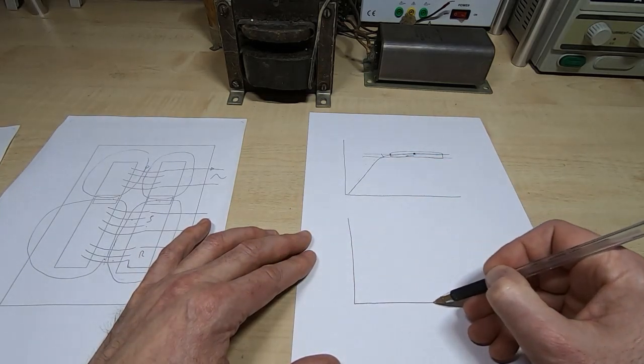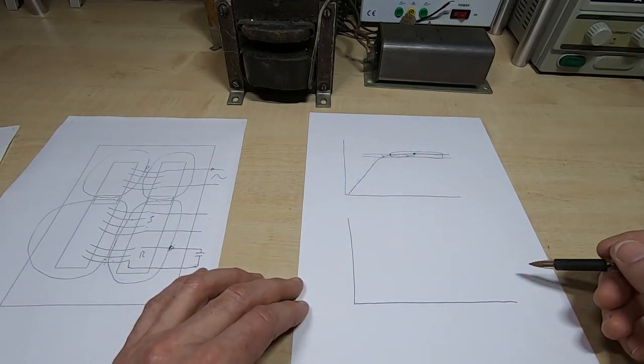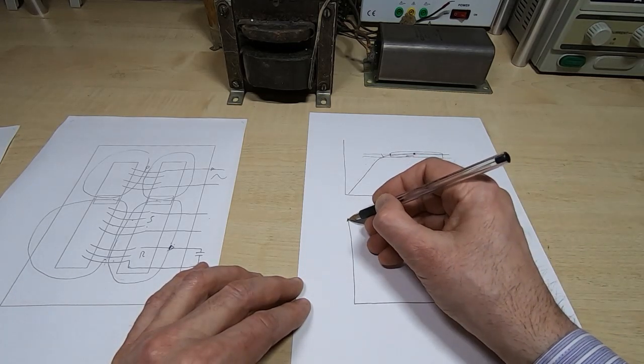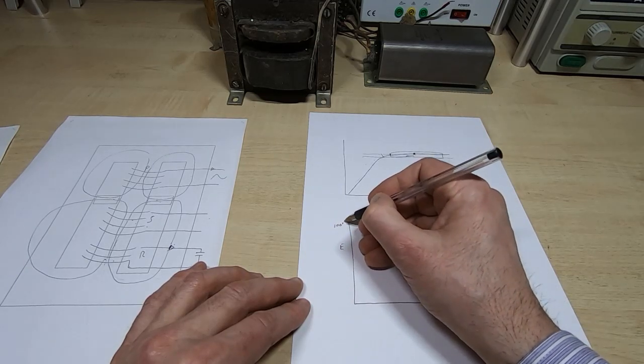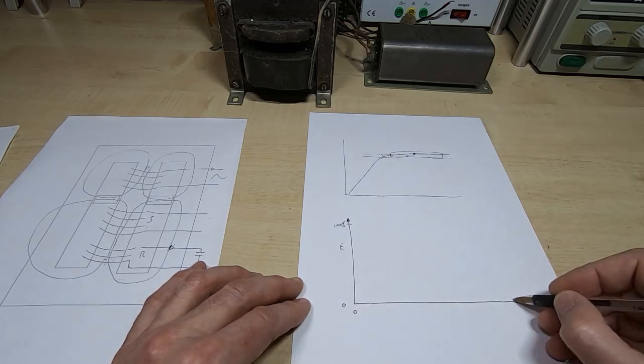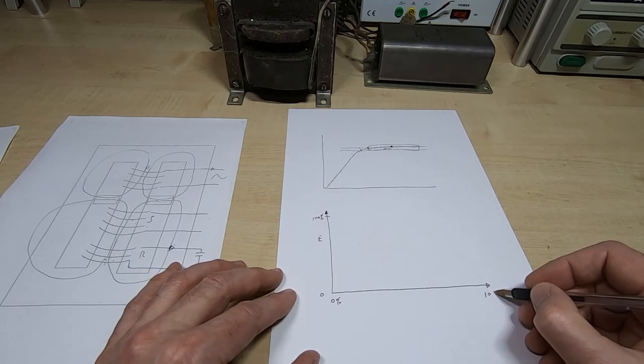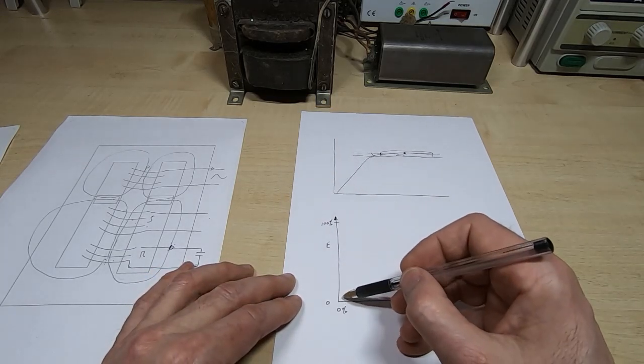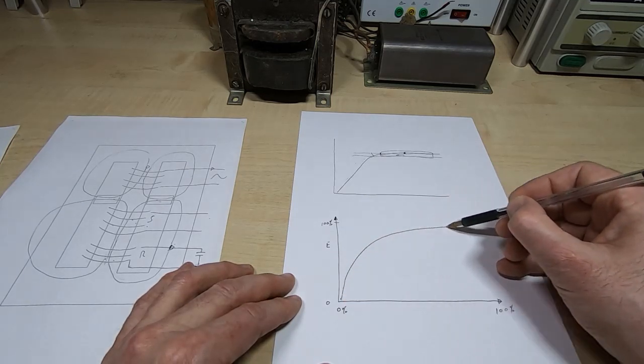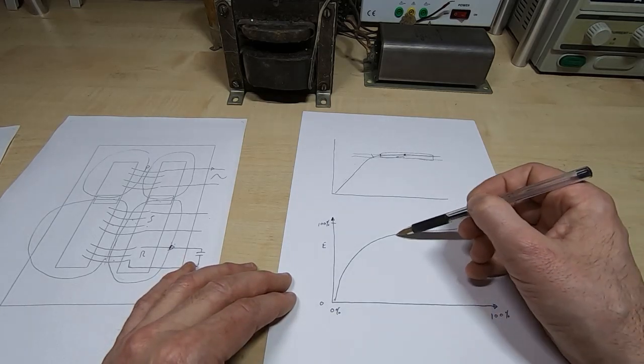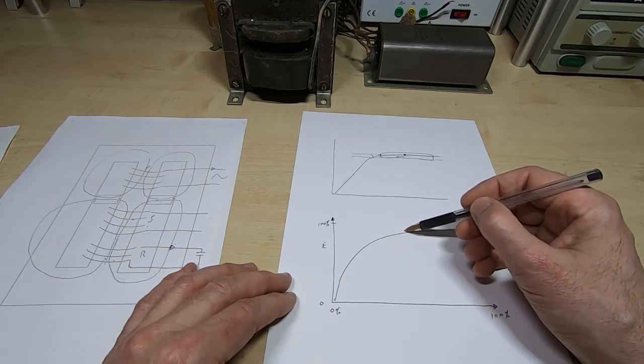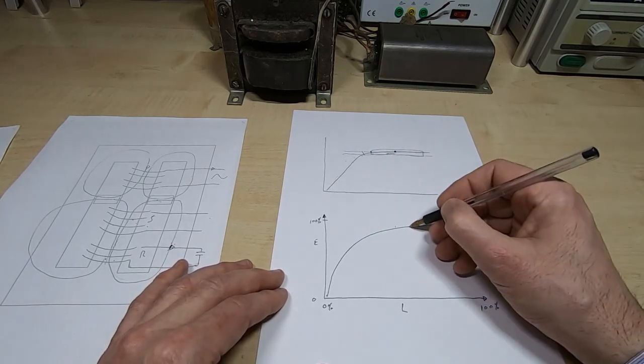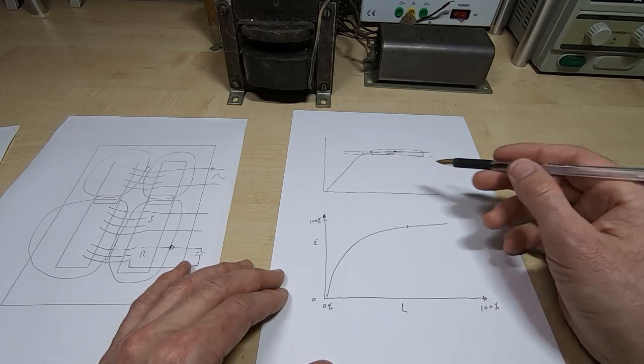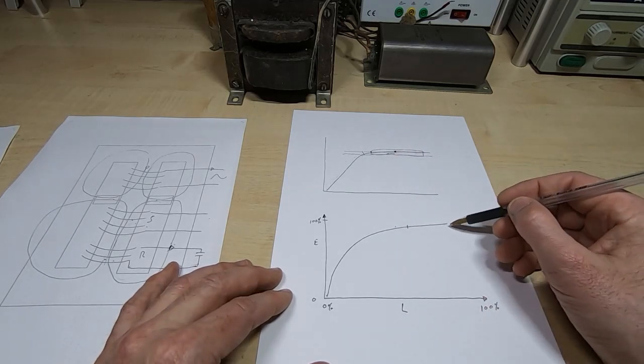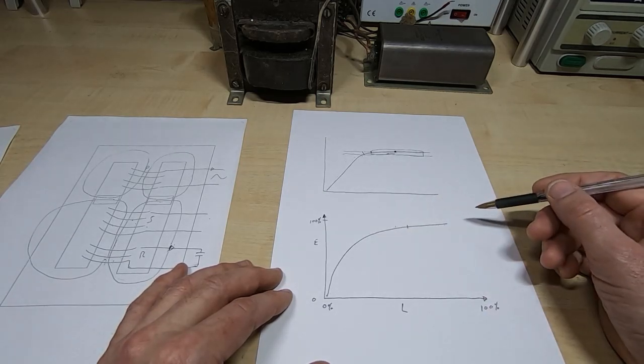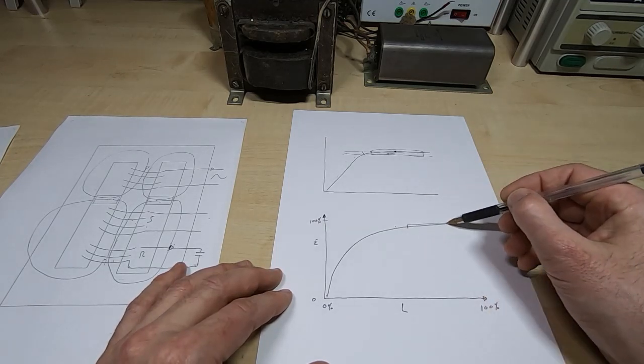If we draw that in terms of load and efficiency, then if we say this is efficiency as a percentage, 0% to 100%, and load again 0% to 100% load, we end up with a bit of an odd looking curve that looks something like this. Typically with this sort of transformer, anything below about 70% full load will give you very poor efficiency. These transformers can be upwards of 90% efficient at full load, but at 50% load they might only be 40% efficient, because they need to operate in a very limited range.